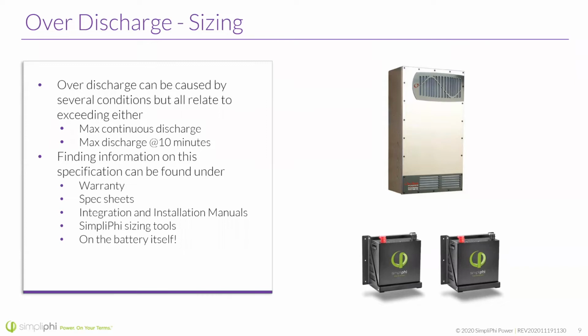That will make sense when I talk about sizing of inverter. I harp on inverter sizing a lot when it comes to our standard Phi batteries. A lot of people will say, well, I know the loads are so minimal, it won't matter. That's completely fine if that's the direction, but over discharge has to be caused by exceeding these limits. So if we see over discharge, even if you think your customer didn't push the battery too hard, they have to have done something to cause this over discharge event.